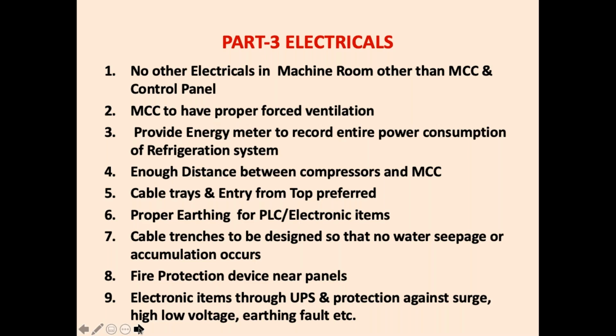Always provide cable trays and entries from the top of the panels. This is preferred so that these are visible to you. Don't run them through the trenches. If you run them through the trenches, they will be flooded with water. They will be full of dirt and dust. They can even be eaten up by rodents like mice, and you will not know till the accident takes place. So your wiring, piping, electricals should be visible. So always take the electricals from the top.